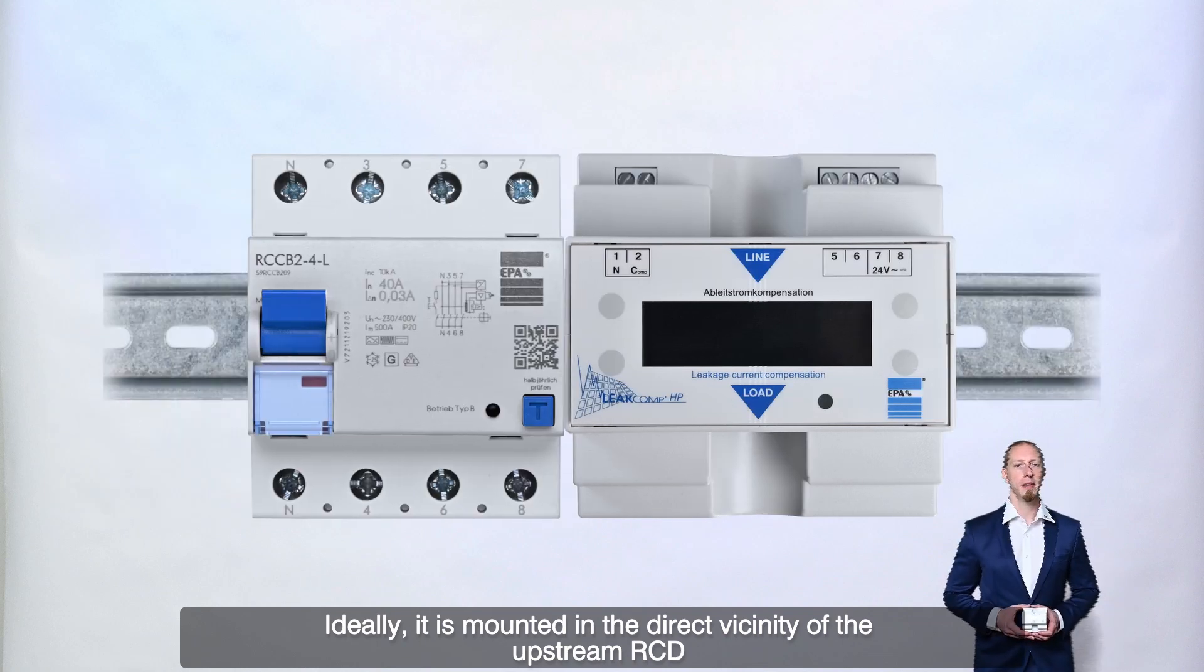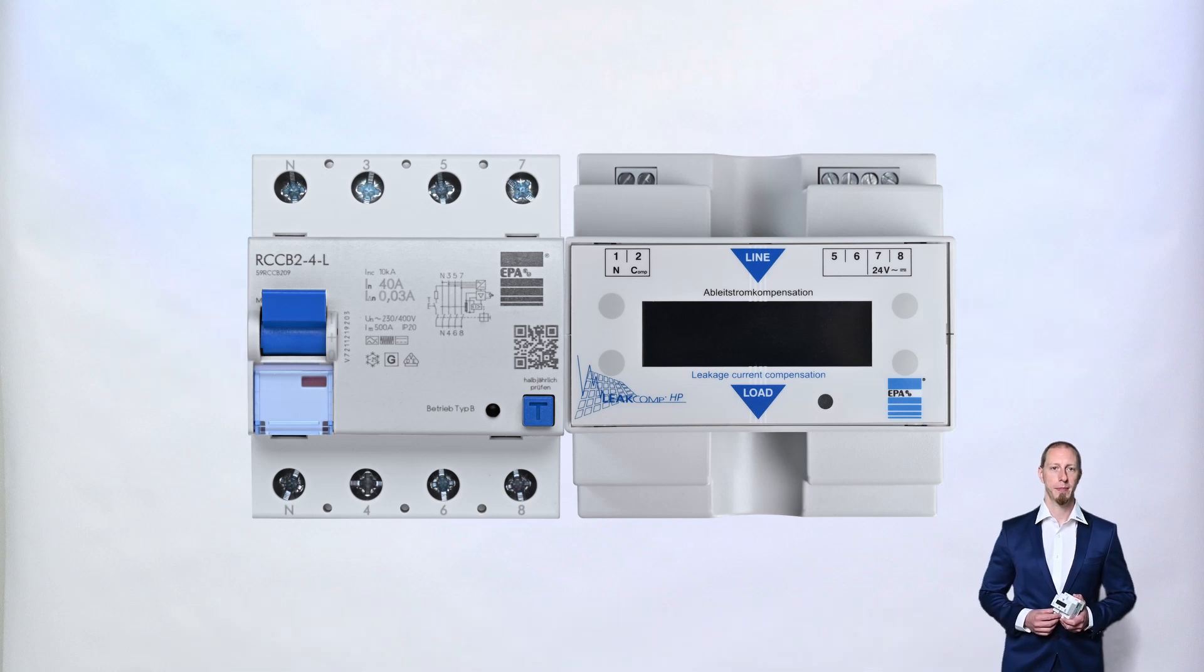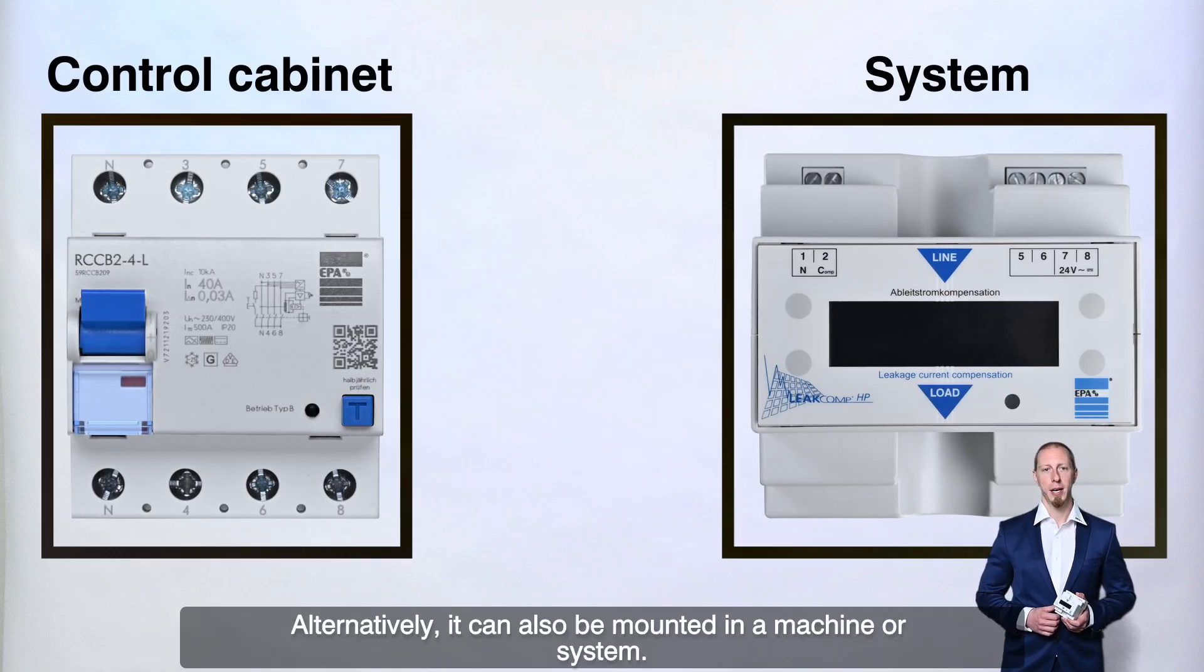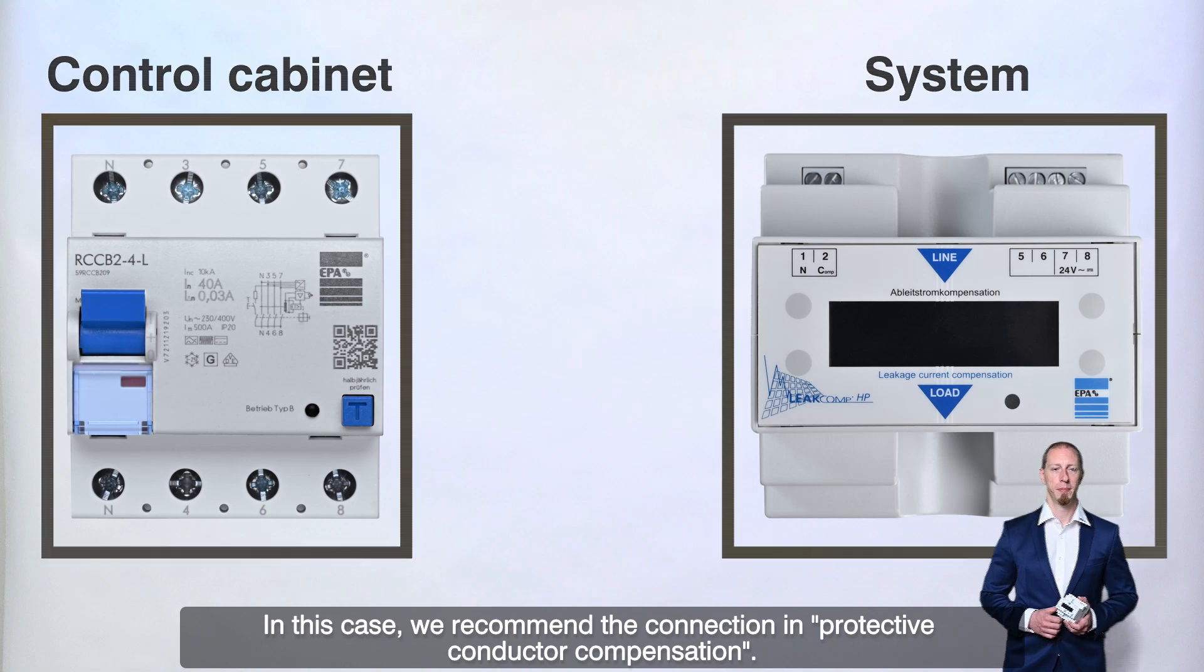Ideally, it is mounted in the direct vicinity of the upstream RCD and connected in direct compensation mode. Alternatively, it can also be mounted in a machine or a system. In this case, we recommend the connection in protective conductor compensation.